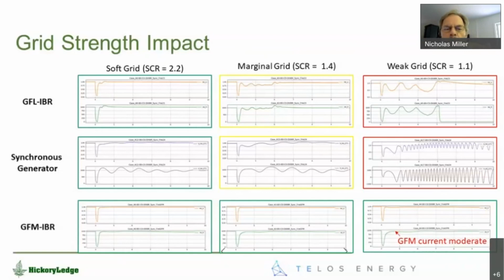The top row is for a current state-of-the-art grid-following inverter, best in class of what you've got on your system. For the pretty soft grid on the left, it behaves well. In the top center, it makes it through this event, but kind of ugly, a violation of NERC voltage criteria, so it's not truly stable. On the right, you see it flogging at about 1 hertz and finally failing.